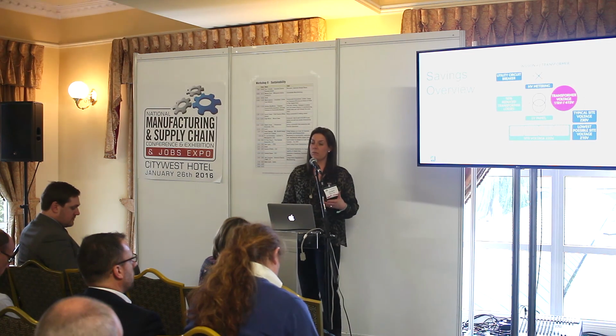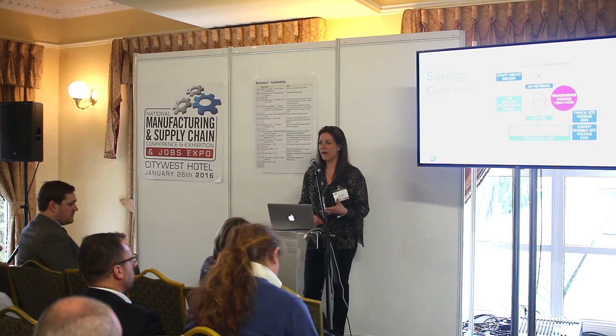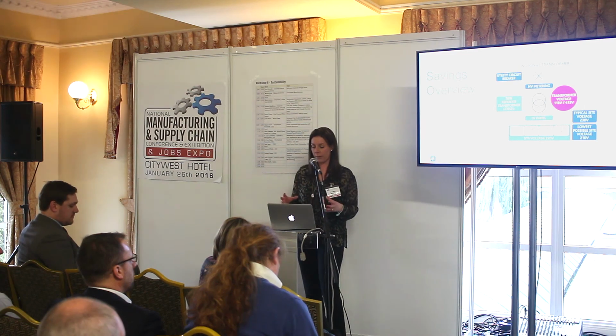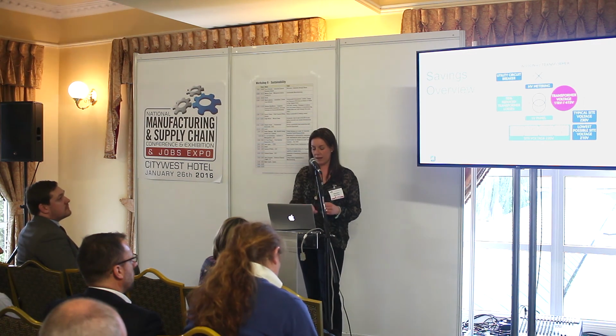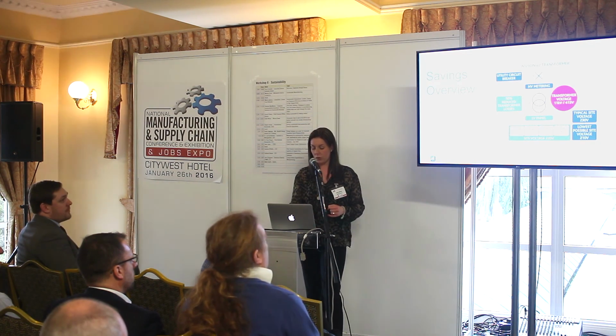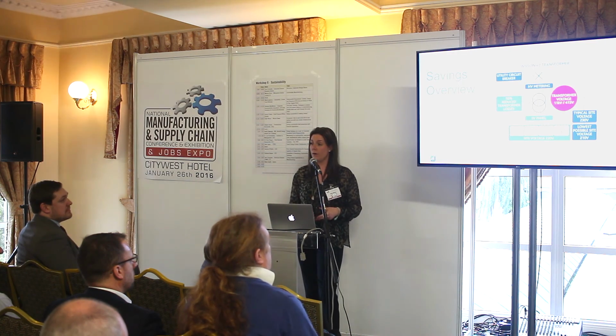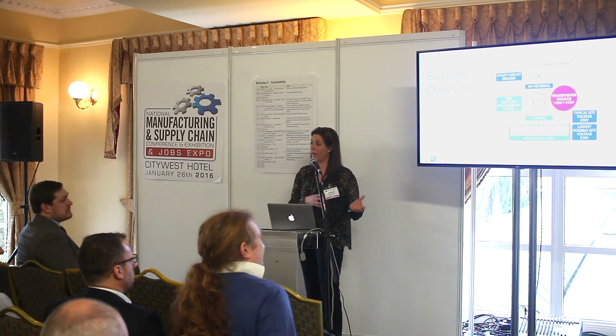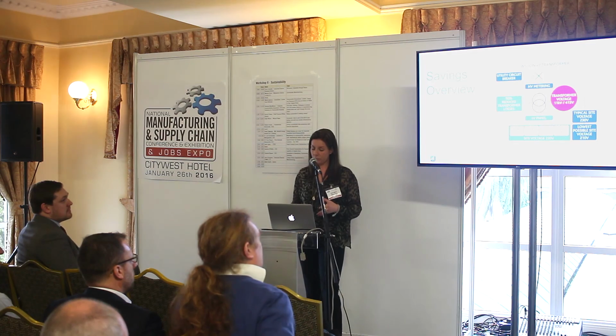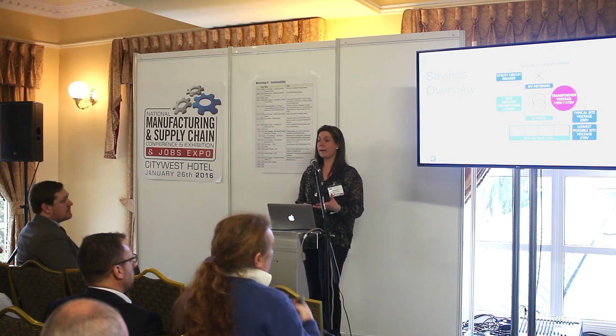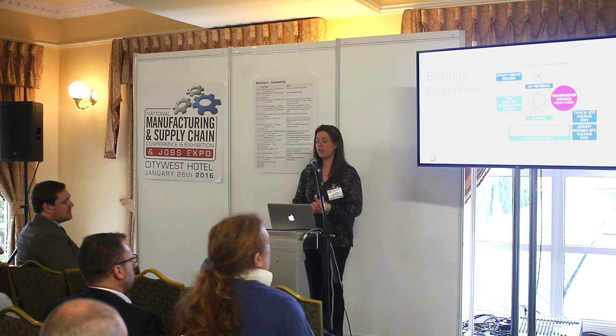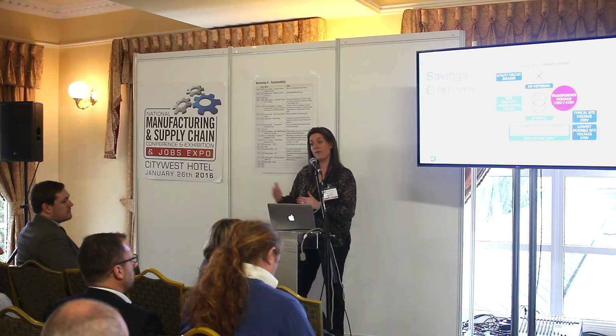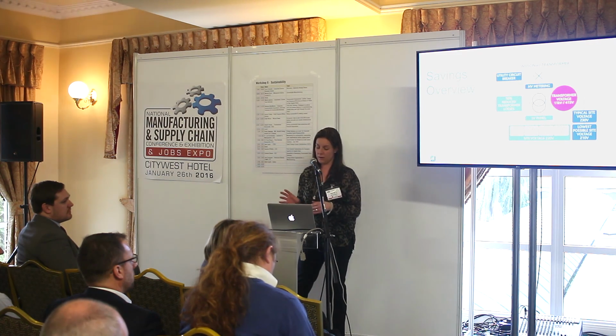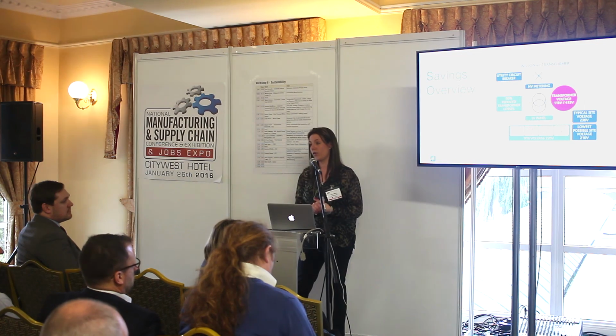So the reason why this is extremely cost effective is apparent, because you've got one plant footprint on this schematic here. You've got your transformer losses reduced, and you also use your tap changer to carry out the voltage optimisation, and you don't have any extra cabling in case some people feel they should put a low voltage optimizer further downstream. You don't need to do that with this. So it is extremely cost effective.